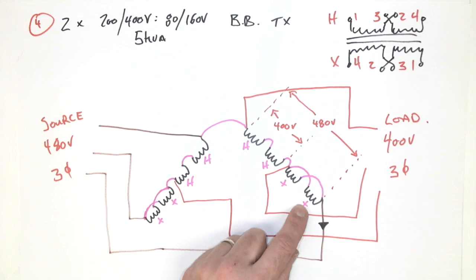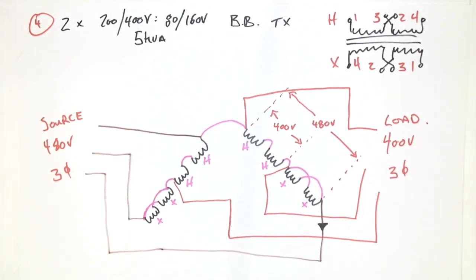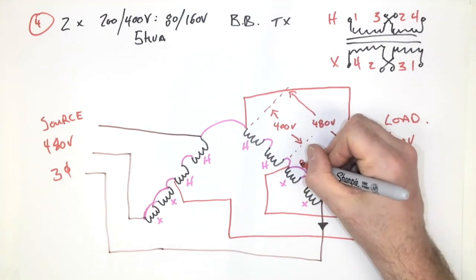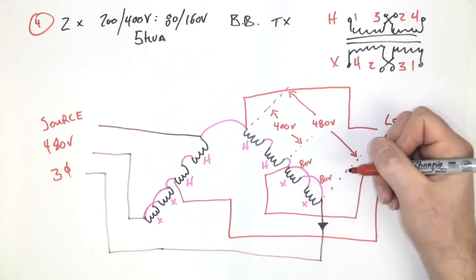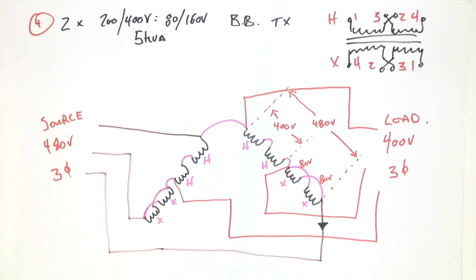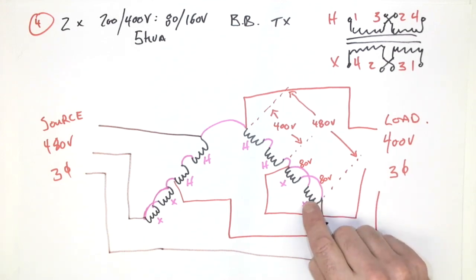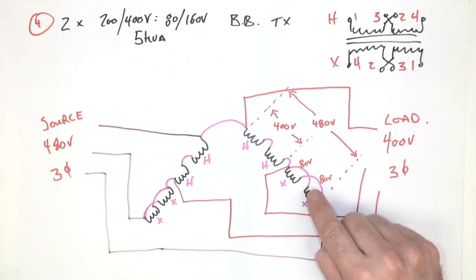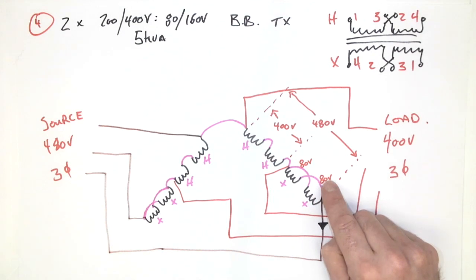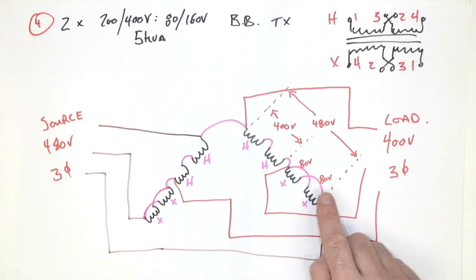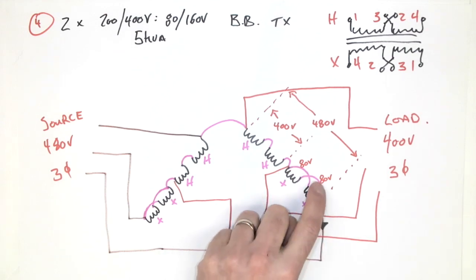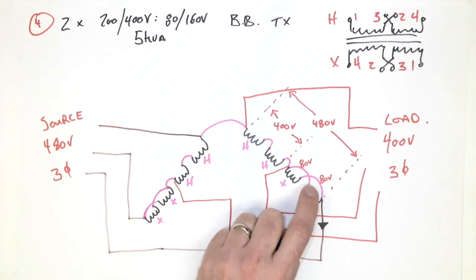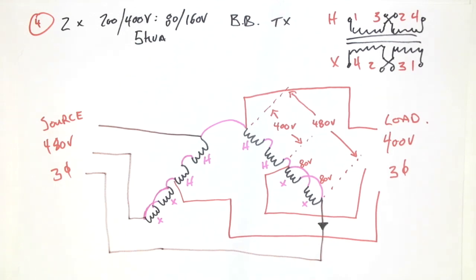Now there's two ways for us to approach this. We can look at the individual voltage of each one of the windings, which is 80 volts, and we can calculate the value of current that one winding will have and then multiply it by 2. Or, since we're using both of those secondary windings at 80 volts, we can take the total 5,000 VA and divide it by the 80 volts. It's really up to you. Because they're in parallel, we are doing both windings in order to work out this current right here. I'm going to choose to use both of these windings together and calculate it at one time with 80 volts.